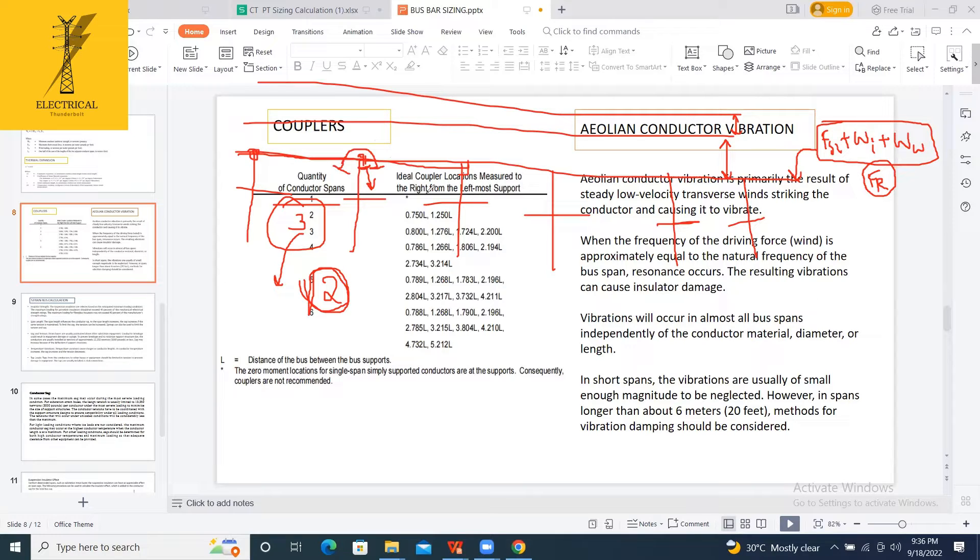And then, if due to some conditions, there might be chances that the natural frequency of the bus and the frequency outside can match. And this leads to, due to some winds, whatever it may be, this may lead to resonance and the insulators will be damaged. To avoid this, I have to place vibration dampers.